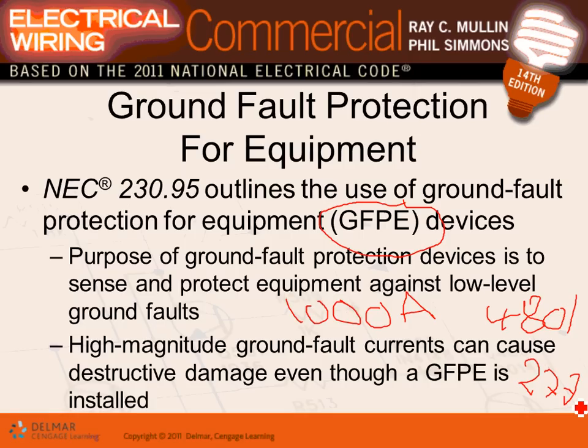Because of this, the code requires you, on the service as well as on feeders, to put a specially designed device called ground fault protection. Did you guys hear me? So when you go to work for somebody else, you're going to see the words ground fault protection. That ground fault protection will protect you from ground faults that are high enough to damage your equipment, but low enough not to be detected by the circuit breakers. Any comments, any questions about the ground fault? Comments, questions? No?